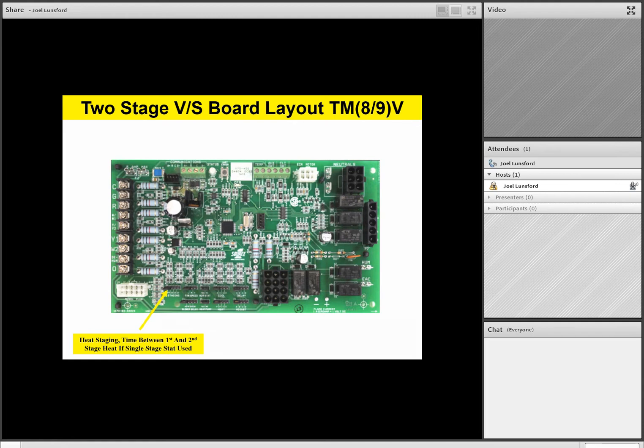So if you're stuck with a single stage thermostat and the board gets a W1 call, and it hasn't satisfied that call in, let's say, 10 minutes, and the staging jumper is set on 10, then 10 minutes later it'll automatically go to second stage to finish that thermostat call. Now remember, team, the only time you're going to use that staging jumper is if you're stuck with a single stage thermostat or you don't have enough wires behind the wall, that sort of thing. It has to be on a single stage thermostat, and it has to be on 10, 15, or 20. Otherwise, you'll never get second stage.